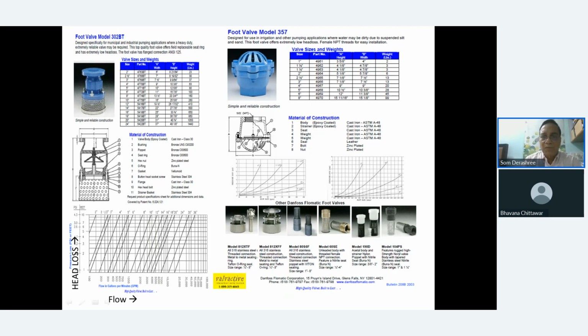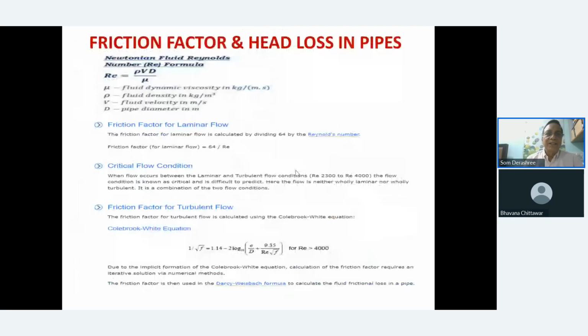This is another type of foot valve, and you see the curves here. It is flow versus head loss for different sizes. So you have to select a particular size of pipe. Since the suction size is normally a liberal size, which is higher, let's say it's 4 inches; the 4 inches will be somewhere here, and then at that particular flow you read off what the head loss will be. So this is how you calculate the foot valve losses.